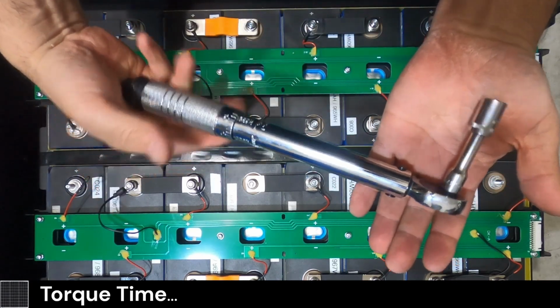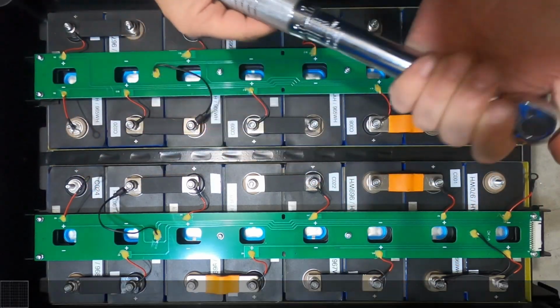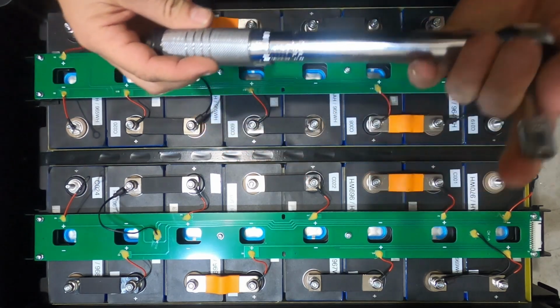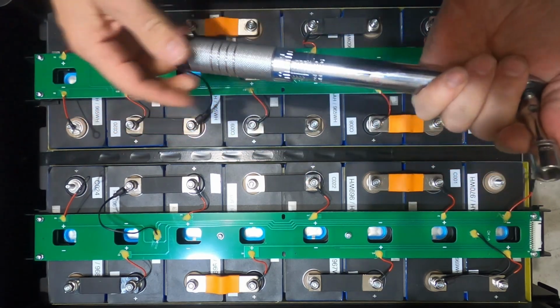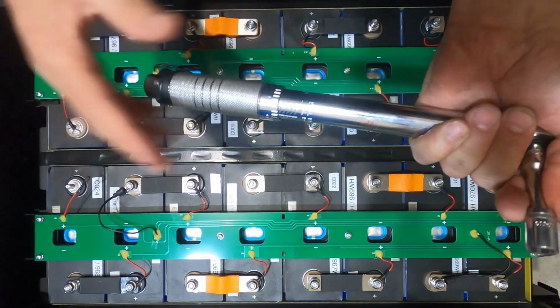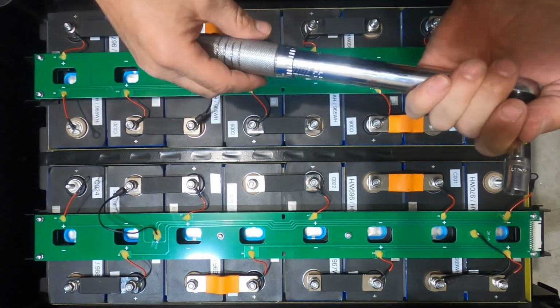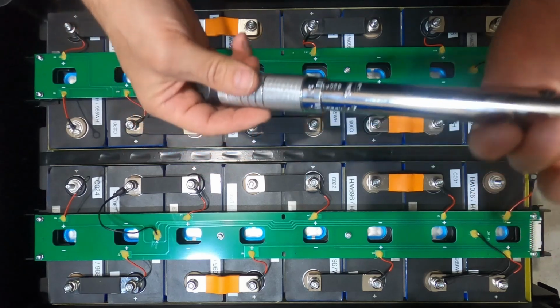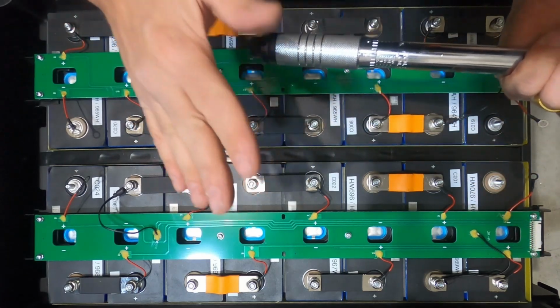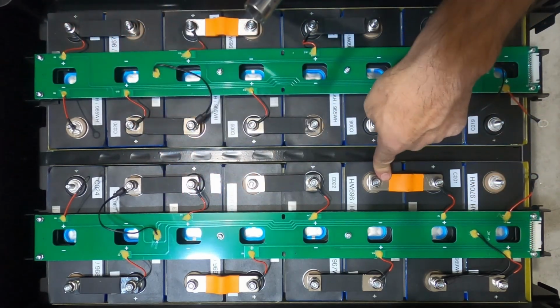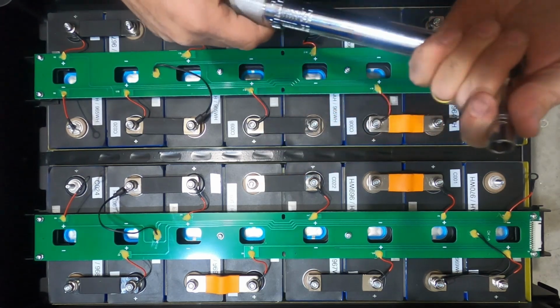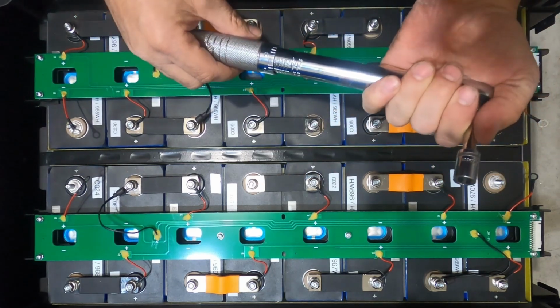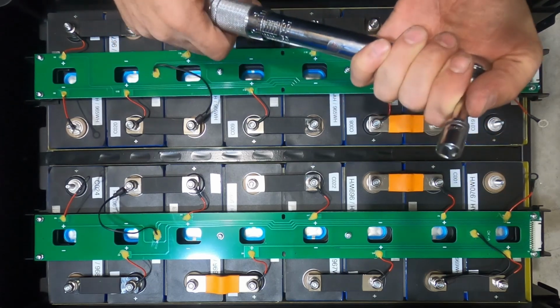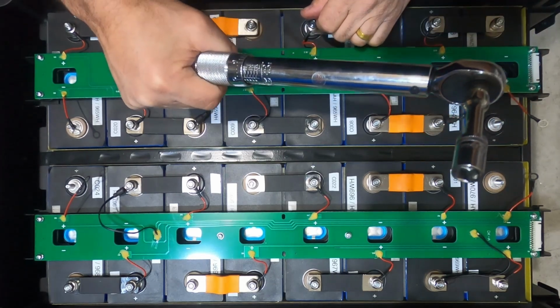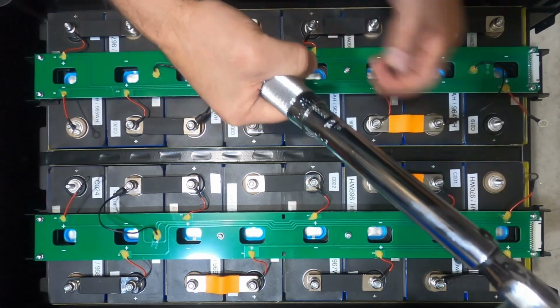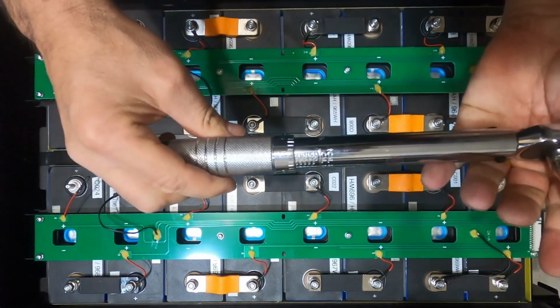Okay, it's torque wrench time. So for the welded studs on these cells, they recommend 8 Newton meters, or anywhere from 70 to 80 inch-pounds. Please check with your cell manufacturer the type of studs you have to determine how much torque is required. Some manufacturers, Chinese manufacturers, will use Newton meters, so you're going to convert Newton meters to inch-pounds if you're using a torque wrench.